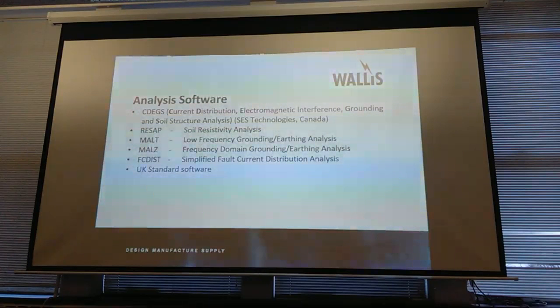You can buy or use whatever modules you want. It's bloody expensive, so to pay for more than what you actually require can be a little bit expensive. So we find that in the UK, these are the modules that we use the most. RESAP is the soil resistivity analysis software, and that's where we get the raw data from the field. We analyse it in RESAP, and it gives us that composite soil model.